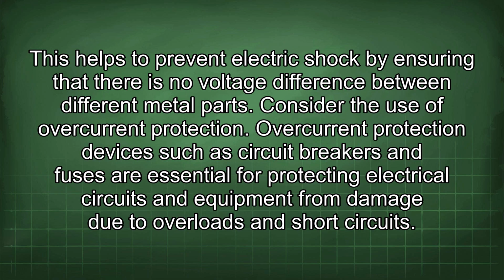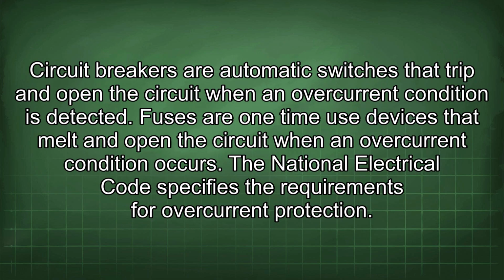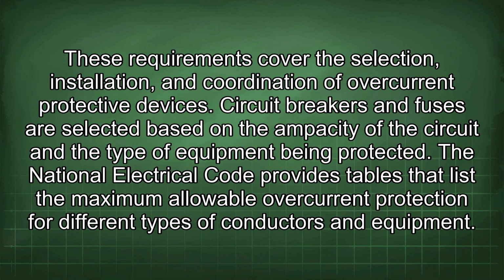Consider the use of overcurrent protection. Overcurrent protection devices such as circuit breakers and fuses are essential for protecting electrical circuits and equipment from damage due to overloads and short circuits. Circuit breakers are automatic switches that trip and open the circuit when an overcurrent condition is detected. Fuses are one-time use devices that melt and open the circuit when an overcurrent condition occurs. The National Electrical Code specifies the requirements for overcurrent protection. These requirements cover the selection, installation, and coordination of overcurrent protective devices.